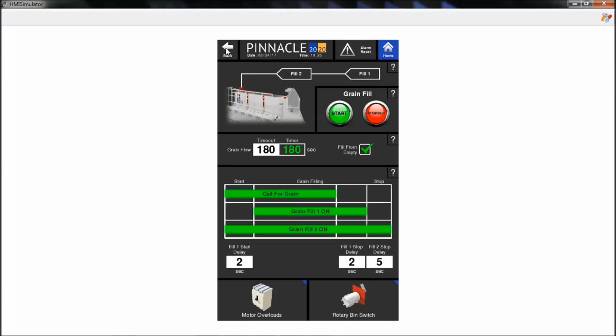So a way for you to indicate to the machine that we're not out of corn, we're just filling up the first time of the day and it's going to take more than 3 minutes, we'll come over here, click Fill from Empty, and then we can hit our back button, come back to the control page, and start our grain fill. Once the dryer is completely full that first time and the rotary bin switch at the top of the dryer detects grain, that checkbox will automatically uncheck and you'll resume normal operation. If you don't check that box, you'll start filling for 3 minutes or however long the timer's set for, and then you'll enter a cool down mode because we'll assume that you've run out of corn.